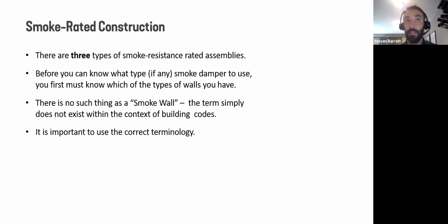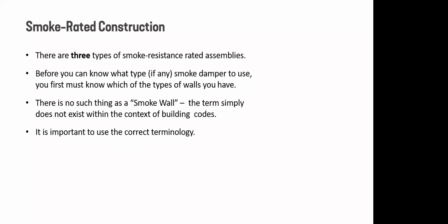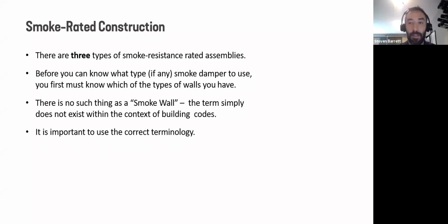I want to say IBC allows it, but requires fire and smoke dampers at the exit and entry into the shaft, so that you can have offsetting shafts, but your duct has basically left the shaft. So you need the combination fire smoke damper. It runs horizontally, above ceiling or wherever, enters a new shaft, another fire and smoke damper, and then continues up. So hopefully I answered the question. I think that's what you were asking. I think so. That was all we had for this section for the moment. Thank you. Okay, great.